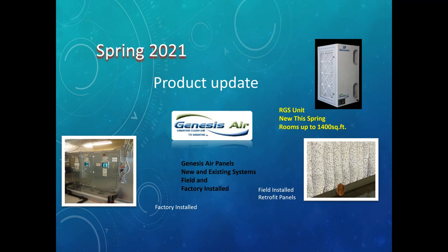Our panels—there's a picture in the bottom right—look like a poorly pleated filter that's been painted white without covering the holes. That's because, number one, we're not a filter. We don't want to capture anything, similar to an evap coil. Because we're doing energy transfer on that panel, we want to try to keep it clean.